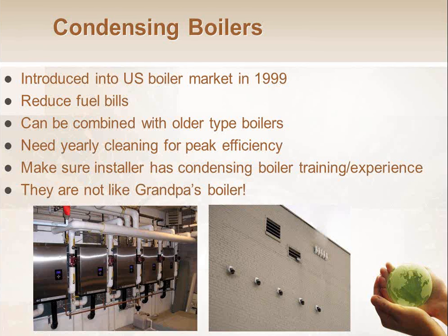For example, you see over here on these 5 boilers we got, let me get my John Madden out here. We got 5 boilers here, 1, 2, 3, 4, and 5. And those guys all have their own individual intakes for combustion air, and they all have their own exhaust pipes as well. You can see where the old louvers were in this picture for bringing in combustion air and so forth. When you switch to these condensing boilers, pretty much for the most part, every boiler manufacturer is going to have one generally PVC intake and exhaust per boiler. So you're probably not going to be sharing anything anymore in terms of exhaust stacks.